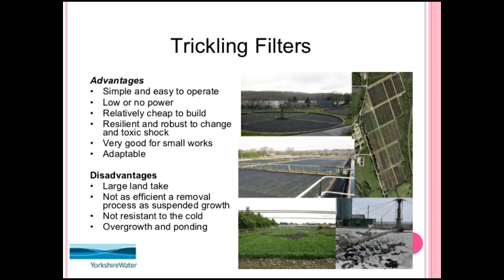Now the advantages and disadvantages of trickling filters. Advantages: it is very simple and easy to operate. It requires low power. It is relatively cheap compared to others. It is resilient and robust to changes and toxic shock. It is very good for small-scale work, meaning it can be used in small-scale industry, and it is adaptable. These are the advantages of the trickling filter.